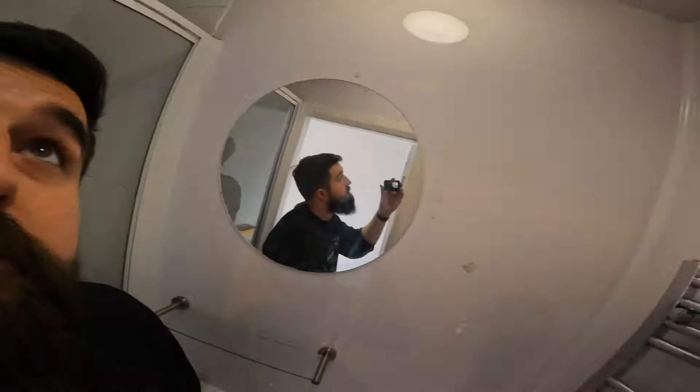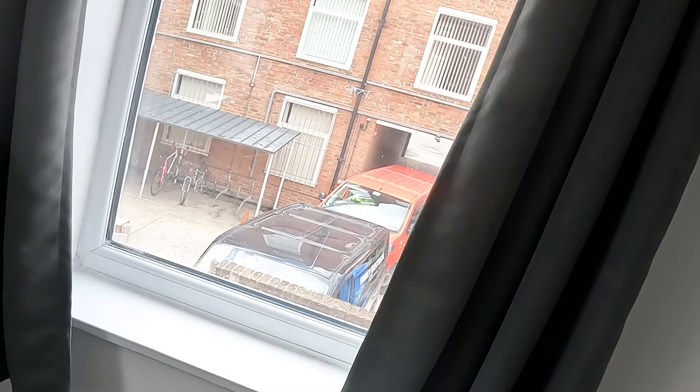Here's one - that there would be a fail on the pull cord. The pull cord thing snaps. What it's supposed to do is have a piece of plastic where you tie off one end of the plastic string and the bottom as well, so you've got electrical separation. If it gets wet, essentially this whole string could be wet into the pull cord gubbins where the live and neutral is. You're supposed to have that electrical separation so if it's steamy and wet in there you're not just conducting straight into it. I'd rang Napit about this before and they said yeah, it should be on there. So we'll have to swap that pull cord over.